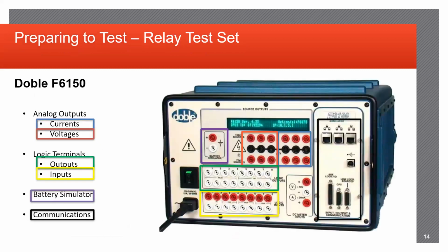So looking at this, this is a Doble F6150. This is a pretty standard piece of equipment for relay testing, especially on the new SELs, any GE relays as well. It's common for new equipment to be tested using this 6150 because it's not only compact and easy to use, but the software itself is fairly straightforward for the most part after a couple test runs.